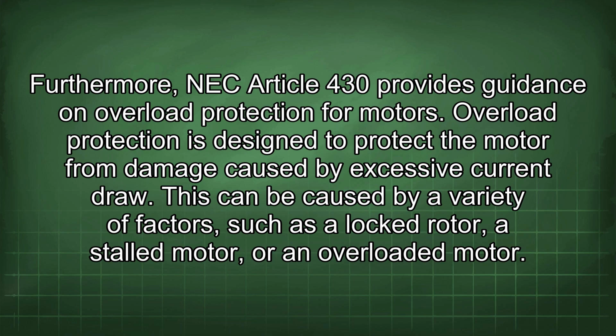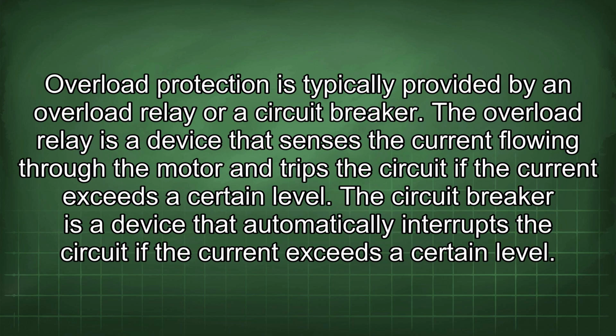Furthermore, NEC Article 430 provides guidance on overload protection for motors. Overload protection is designed to protect the motor from damage caused by excessive current draw. This can be caused by a variety of factors such as a locked rotor, a stalled motor, or an overloaded motor. Overload protection is typically provided by an overload relay or a circuit breaker. The overload relay is a device that senses the current flowing through the motor and trips the circuit if the current exceeds a certain level. The circuit breaker is a device that automatically interrupts the circuit if the current exceeds a certain level.